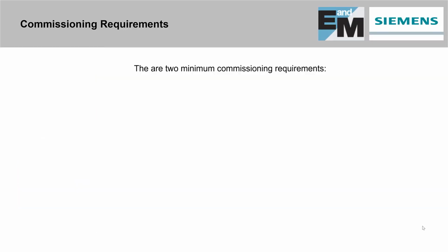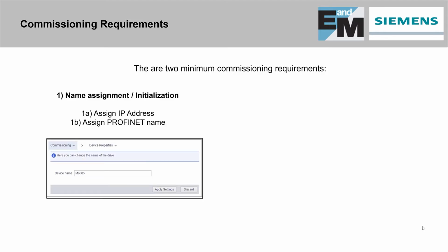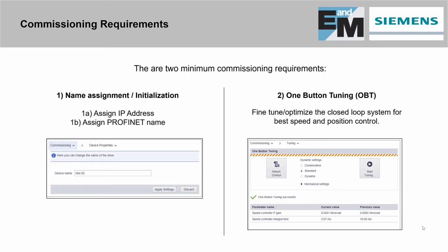Since the one cable connection and the PLC set up a lot of the S210 parameters, there is very little for you to need to commission yourself. You can be up and running in just 2 steps. First, you need to set up the IP address and Profinet name to communicate with your Siemens PLC. And then once the motor has been installed in your system, perform a quick one-button tune to properly set up the closed-loop control.